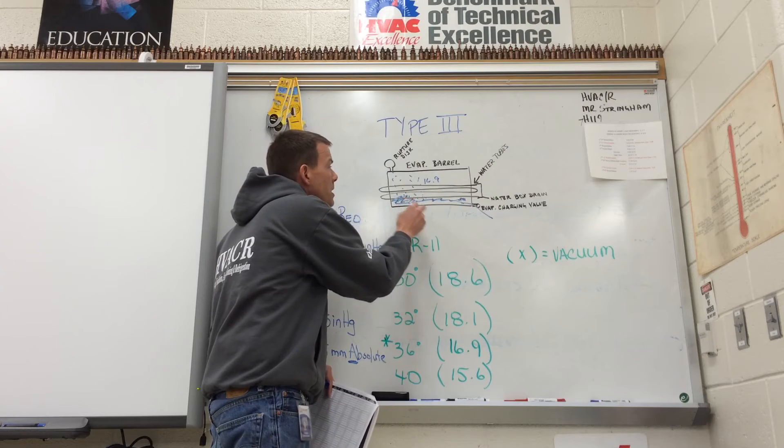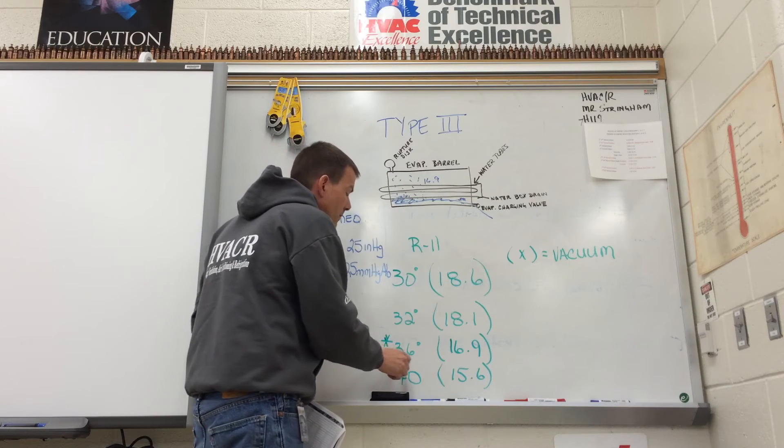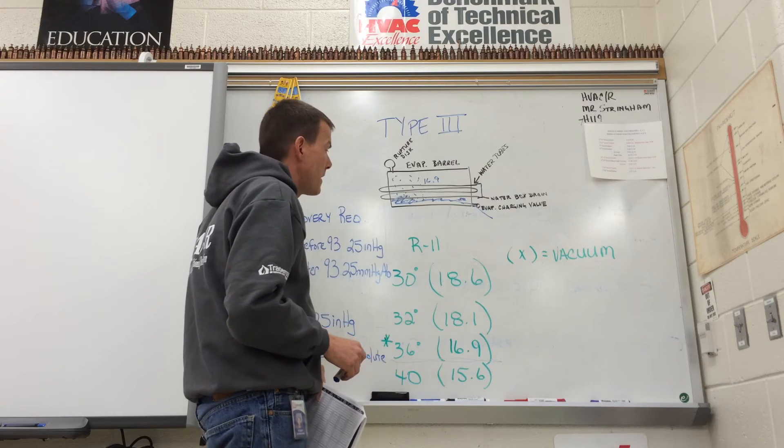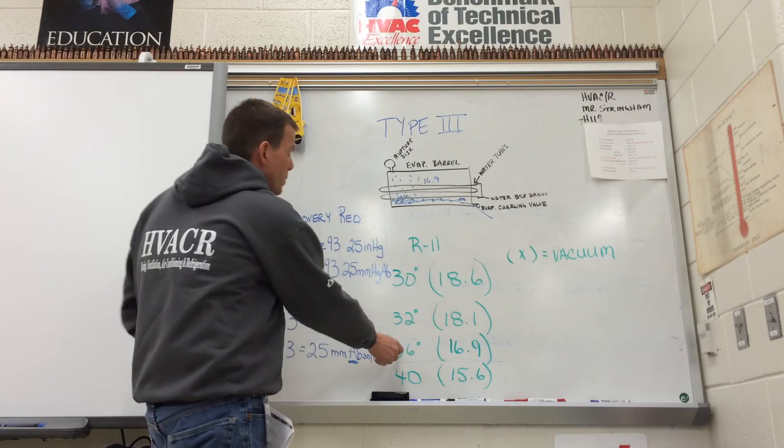So they want to make sure that you know to charge with a vapor so the saturation temperature of R11 refrigerant gets to 16.9 inches in mercury vacuum. And they don't give you any of these numbers. You just need to know that. I think they put that in the text.